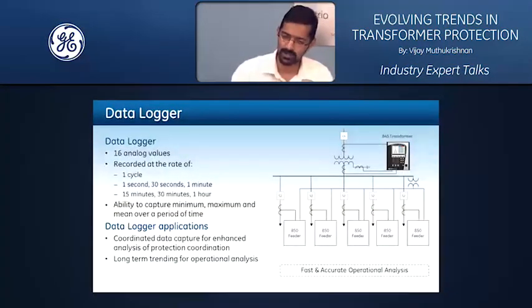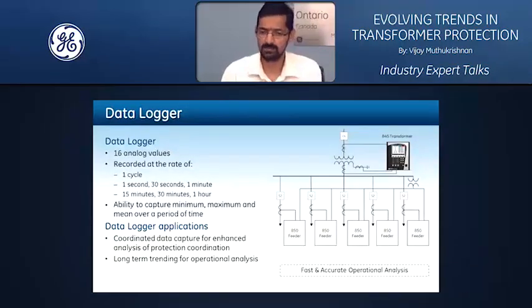Now, we talked about the transient recorder being useful for fault conditions. At the same time, the relay is collecting a lot of information, be it electrical or thermal characteristics, temperature, etc. If you have an ability to continuously log and trend them, you can build custom applications to trend certain parameters. For instance, load current and temperature over a period of time. See what happens. How does it trend? Do you see any varying trends that are worrying you? So you can build some applications in terms of operational effectiveness of your transformer asset. Also, from an engineering perspective, you can actually do time coordinated sampling of calculated parameters across multiple relays and try to validate your protection coordination, for instance, which is another application where you can use this.